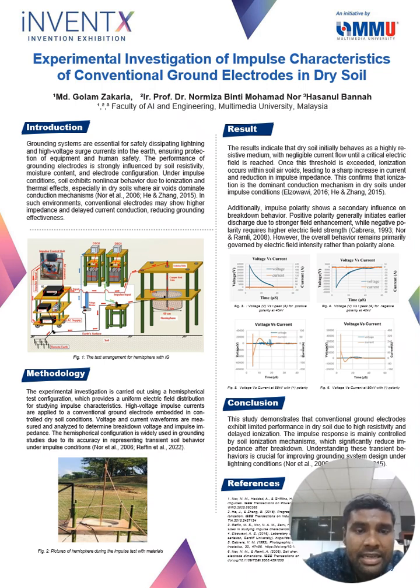You can see here the current level is almost zero, and the voltage graph is high. That means whatever voltage we inject, we get the same voltage but no current, because the soil is showing resistive behavior. So initially it's a highly resistive material. This is the first thing.